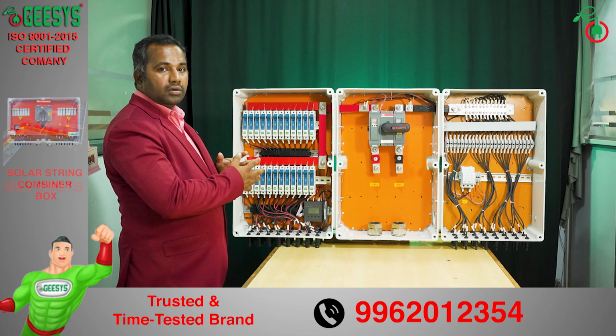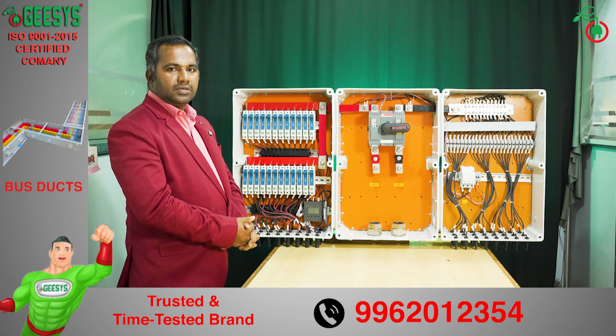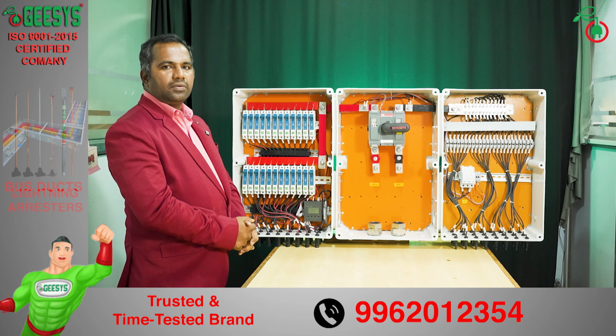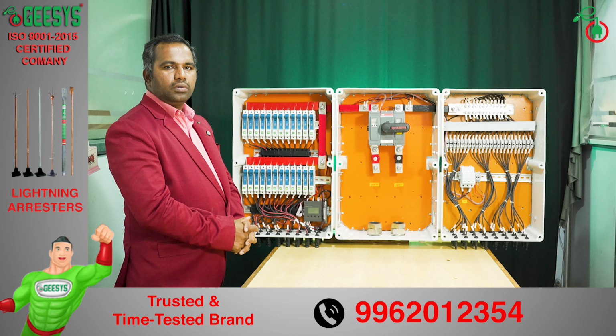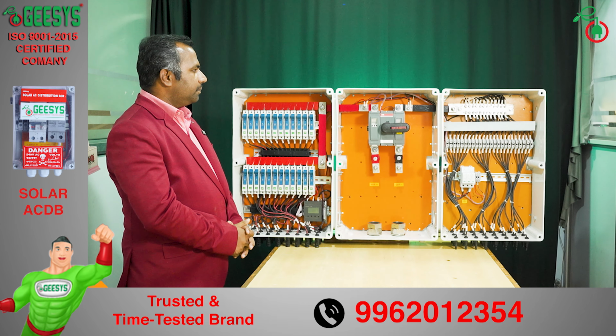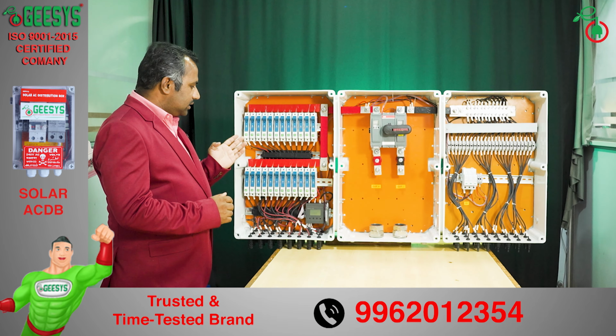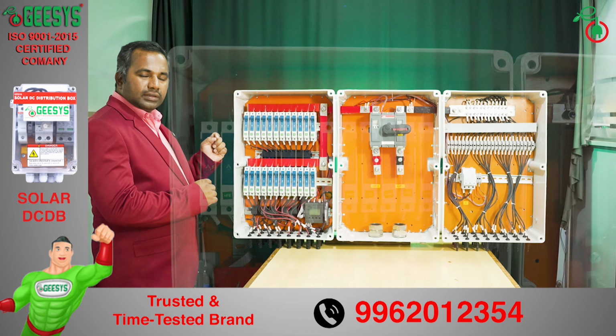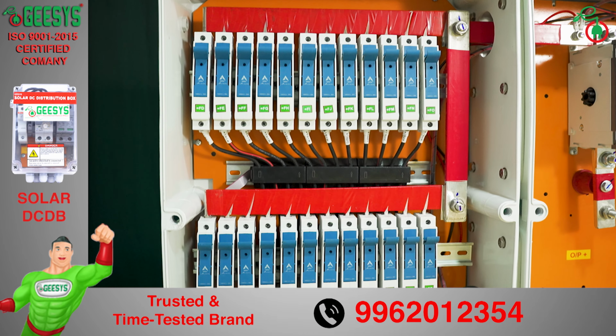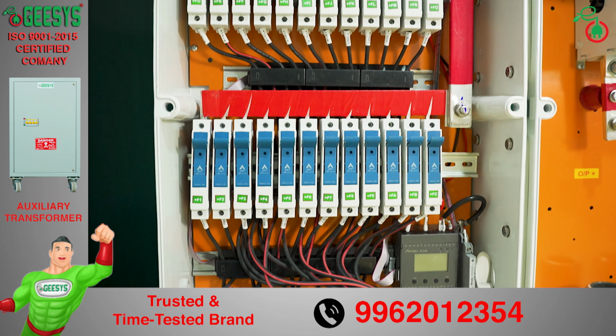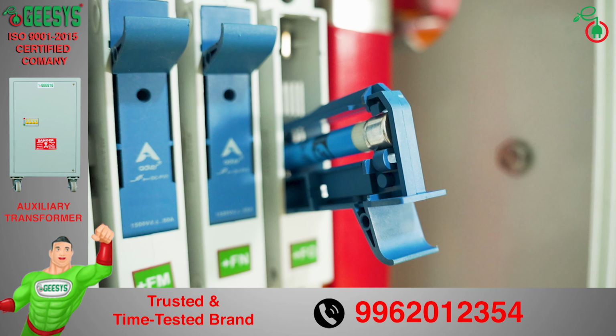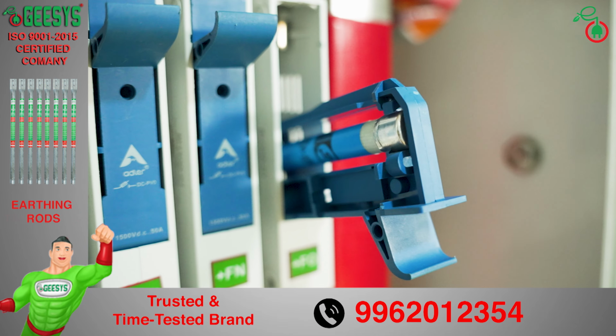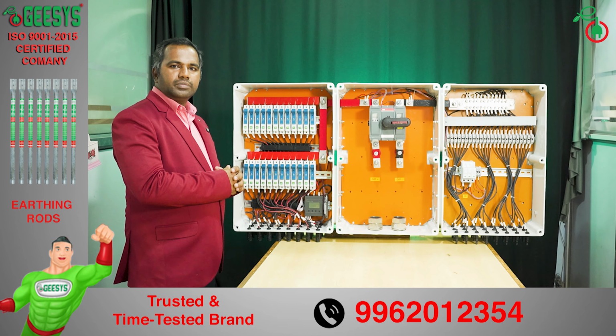This is polycarbonate enclosure tested for IP65 and an impact resistance rated for IK10, and it is certified to IEC 60529. Next we will see the fuses. This is 1500 volt DC rated 30 amps fuse holder. The short circuit capacity is of 30 kiloampere. This fuse holder is touch safe fuse holder which you can operate with your fingers. Inside the fuse holder we used 30 amps fuse links.